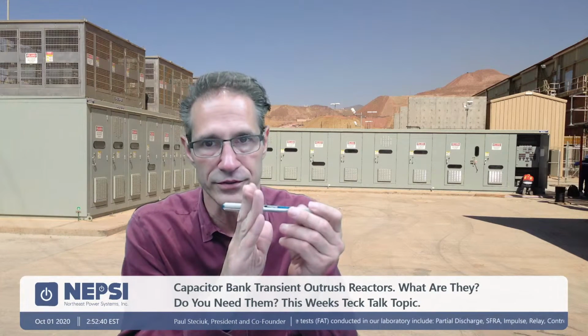And one of those errors might be putting a piece of bus bar up, connecting it, and pushing a bolt through too far. Your manufacturer, the guy assembling the equipment, might use a 3-inch bolt when he should have used a 2-inch bolt. And he has a phase to ground violation that can result in flashover. So we're going to actually do this impulse. Jessica, I think Peter will be with us next week to do that on the factory floor. So we will start here in the office again, and then we'll go to the factory floor and review this impulse test for next week.